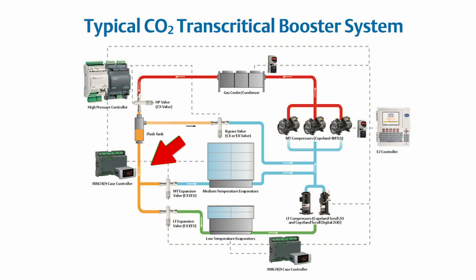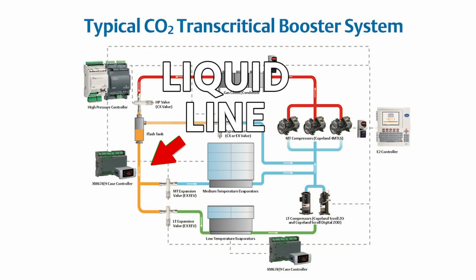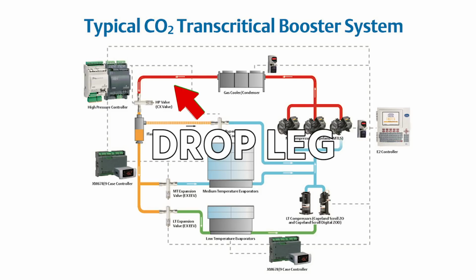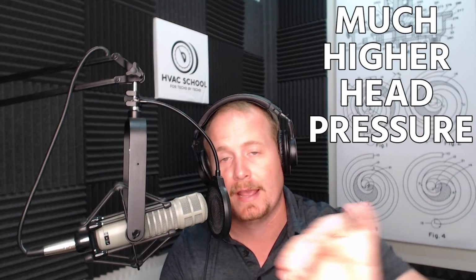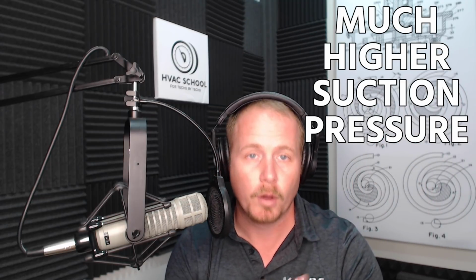Generally we tend to call that in air conditioning the liquid line. But in grocery refrigeration, the line that leaves the receiver is what they would call the liquid line most often. And the line between the condensers and the receiver is what they would traditionally call the drop leg. You'll notice here that you have 400 PSI suction. And that's what you're going to see on CO2. You have much higher head pressure and much higher suction pressure than what we're normally used to.